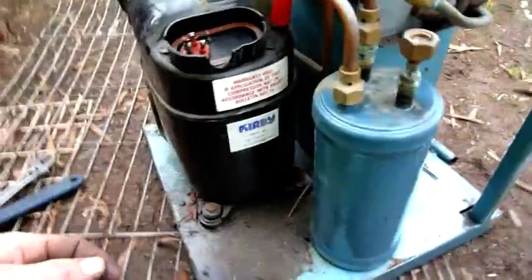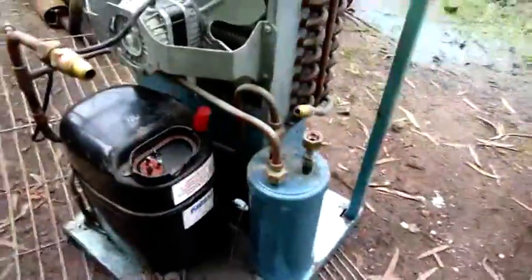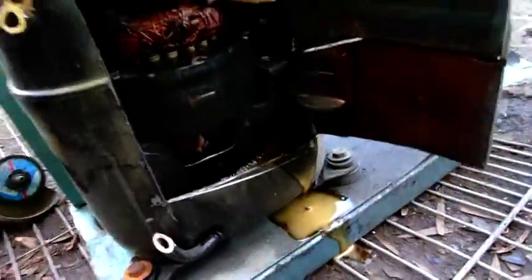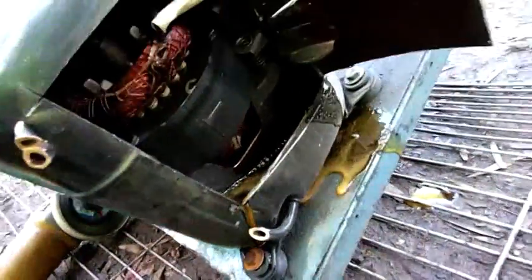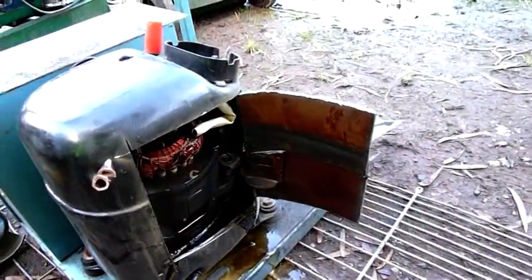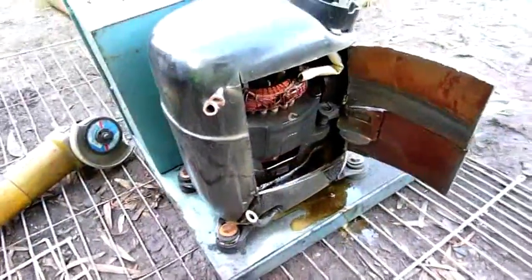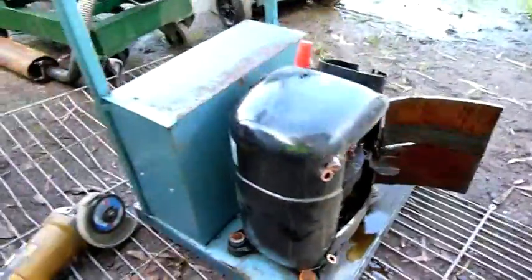Warranty void. I'm guessing warranty doesn't cover using it for recovering nasty old units because I don't think this is an original compressor. Well, I made a door in the compressor and sure enough she's seized solid. The oil that's coming out of it looks worse than the oil in my BMW, and that oil has been in there for six months. That's just evil. Still got a tiny bit of refrigerant evaporating out of it but that pump is just rock hard. It seems to be with these Kirby compressors — they just seize up. Considering what this one's been through, look at all that corrosion. It's been sucking moisture, it's been sucking acid. The windings probably weren't far off but the bearing failed first. These things must eat compressors when you use them to recover dead units because you get all sorts of stuff through the system. Yeah, it's just nothing but rust on the inside. It's dead now.